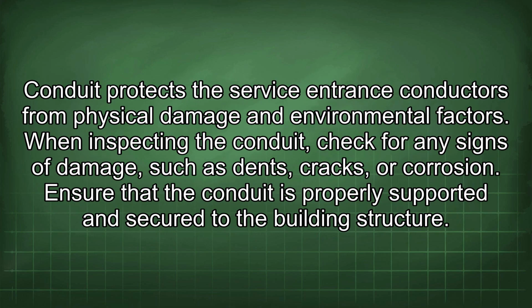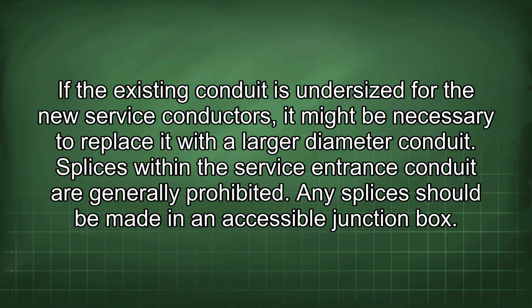Conduit protects the service entrance conductors from physical damage and environmental factors. When inspecting the conduit, check for any signs of damage such as dents, cracks, or corrosion. Ensure that the conduit is properly supported and secured to the building structure. If the existing conduit is undersized for the new service conductors, it might be necessary to replace it with a larger diameter conduit. Splices within the service entrance conduit are generally prohibited. Any splices should be made in an accessible junction box.